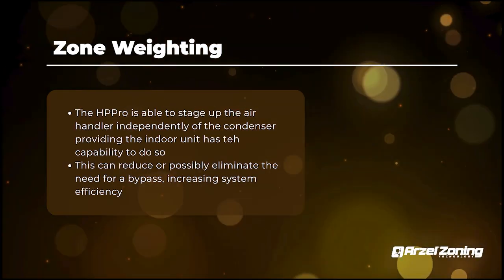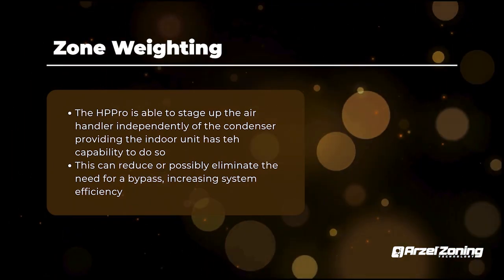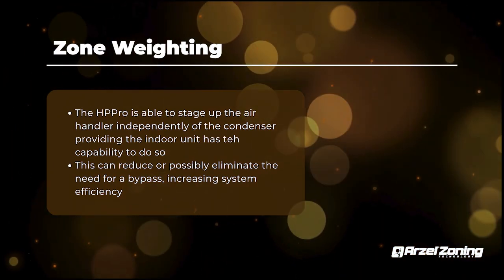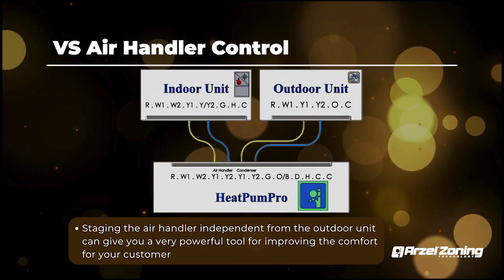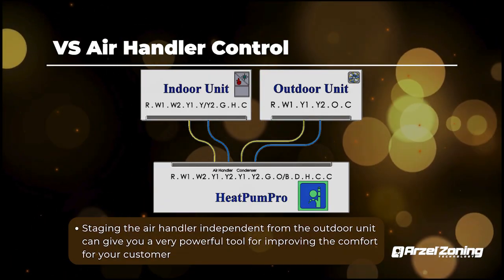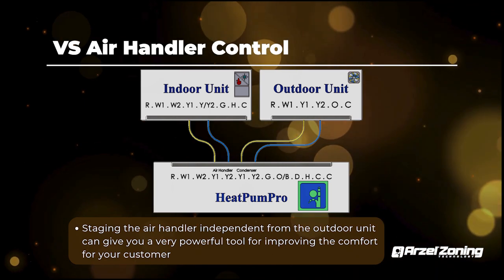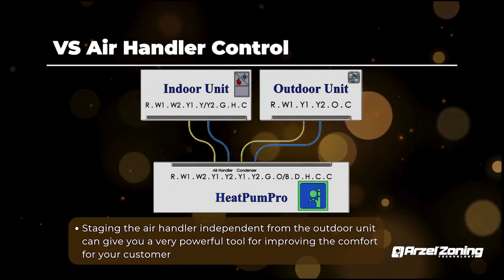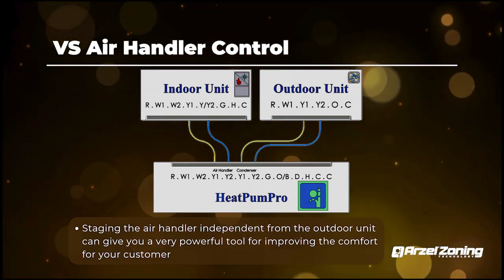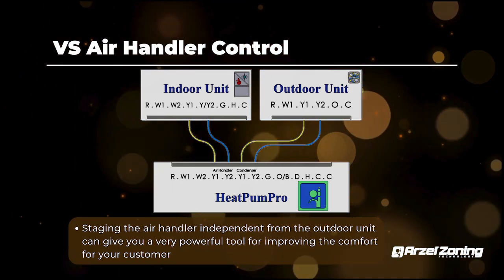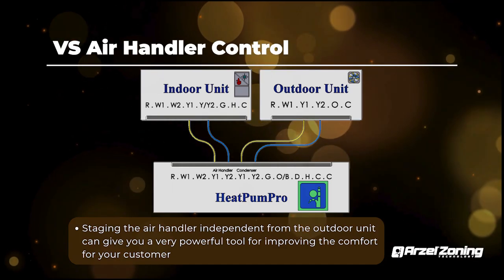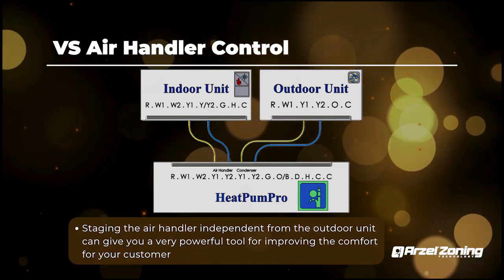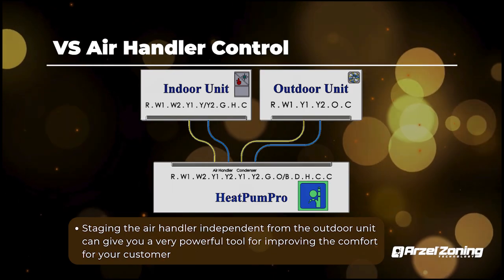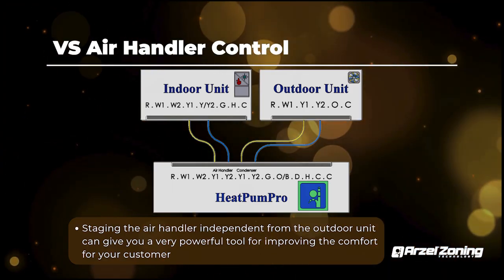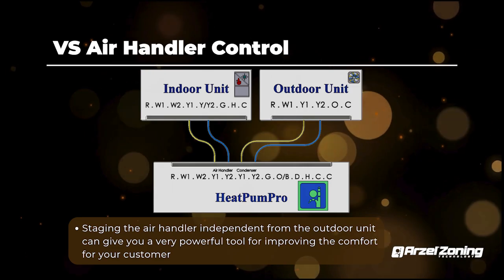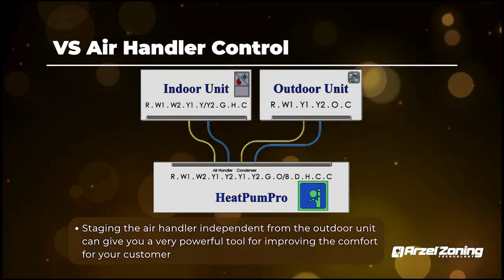And one of the best things, my favorite thing when I was in the field about the HeatPumPro is our zone weighting feature. And really what that does is it allows us to separate our air handler and condenser Y1, Y2 terminals. And then we're actually able to stage those independently of each other. So what it allows you to do is you can actually lock out your second stage blower on your smaller zones and still be able to produce a Y2 on your condenser, which will give you guys longer runtime, better dehumidification, but more importantly, slow that blower down so that you guys can get away from using a bypass or at least decrease the size of the bypass you may need without creating objectionable air noise for the customer.